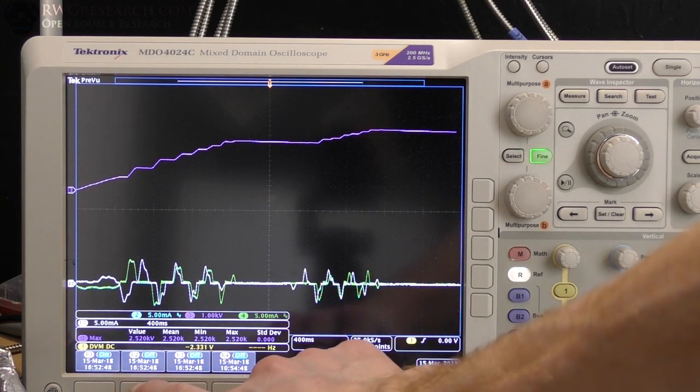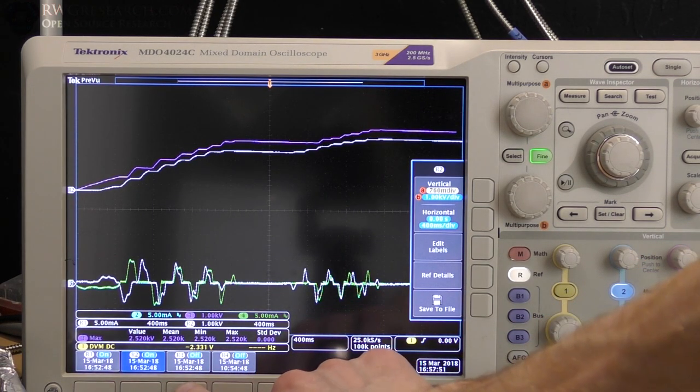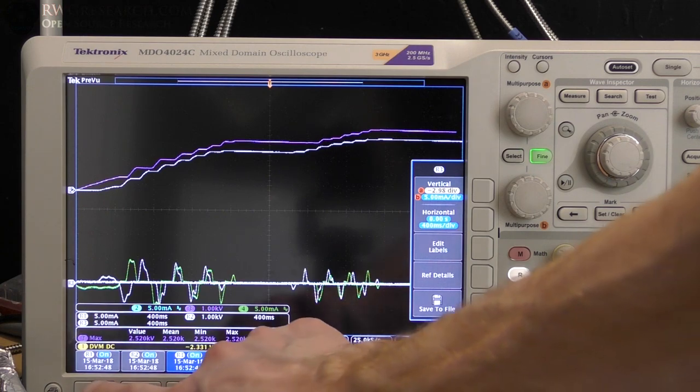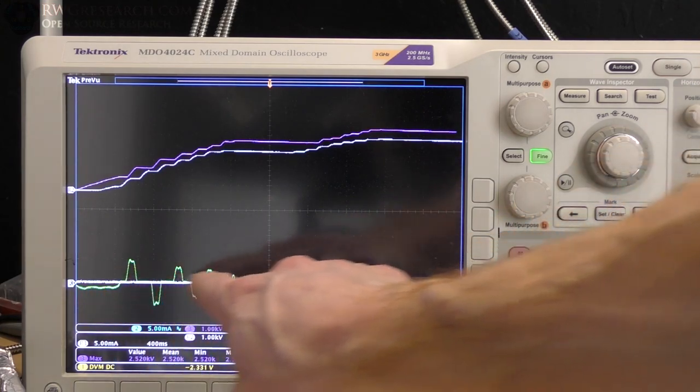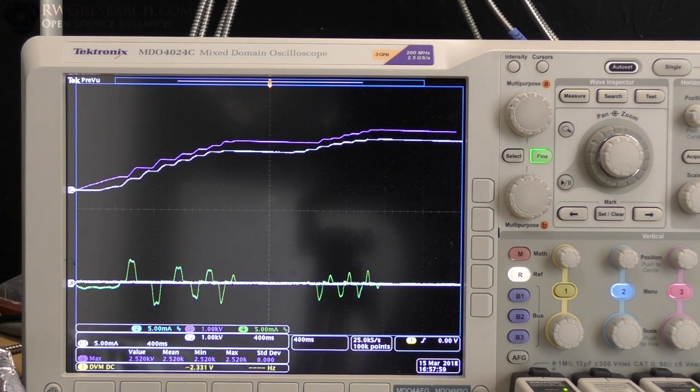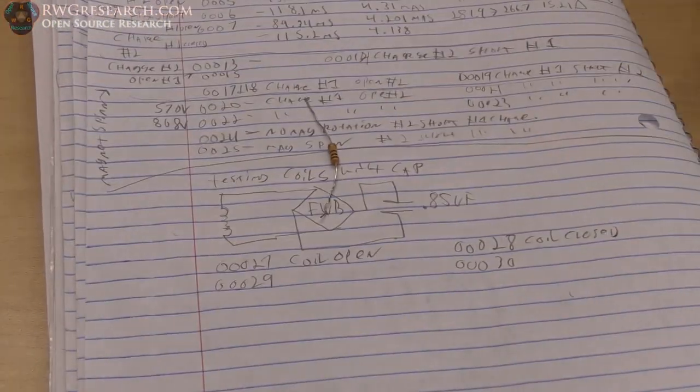Now, if I turn on this one and I turn off this one, you can physically see there's a flat line all the way across there. So that flat line... Pizza's done. Thank you, Riley. That flat line is telling me that there is no current flowing through the open part of this coil. So it is literally an open circuit, right?